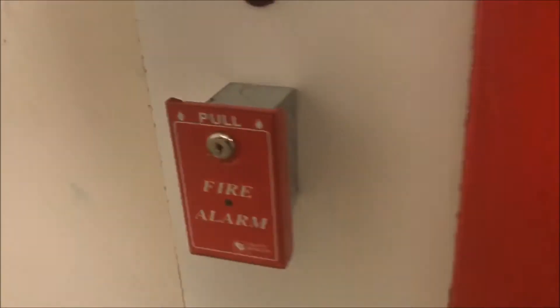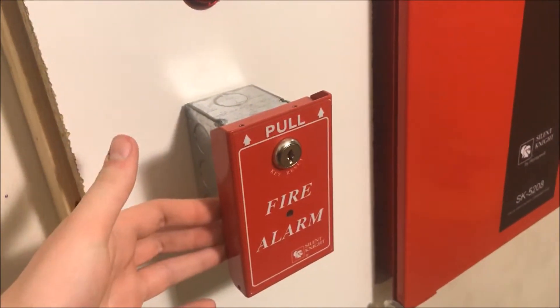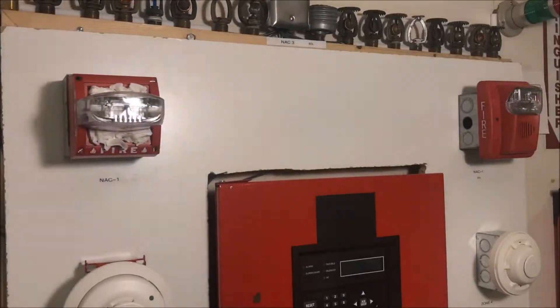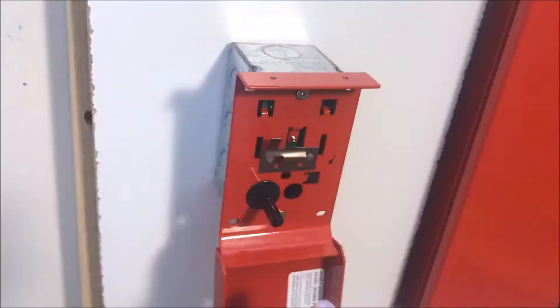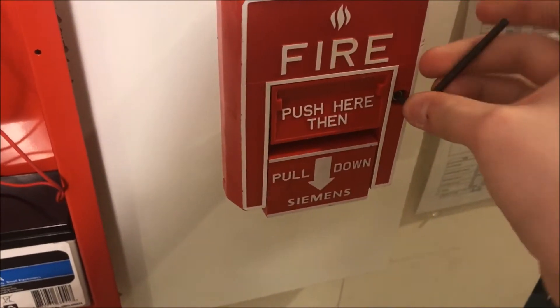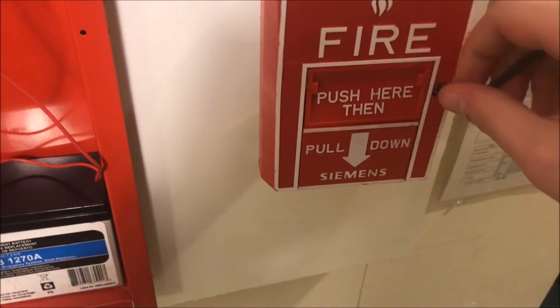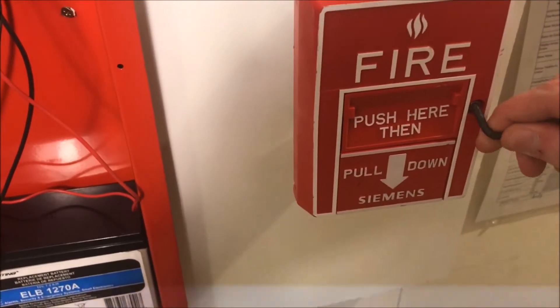We will silence from the external silencer, strobes continue to flash, and we'll pull this one right away in its single action state. Three, two, one - and we will silence that because it's really loud. Now I can put the lift tab on it. Reset - takes the same Allen wrench as the Firelite BG-12s do - just hold open and reset. MS-10B reset, intelligent is gone.